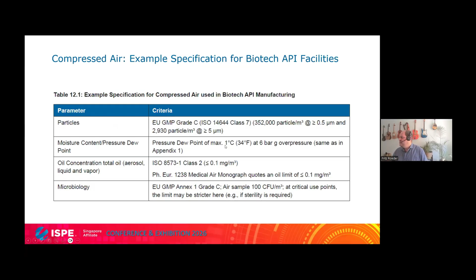Last but not least, we have two slides to go. This is the sterile slide here. The example is somewhat longer, of course. Here we have the clean room down to class A, but we say we don't need class A conditions in our compressed air pipe. We put a base quality of grade C in there, and if you need a higher spec in class B or class A because you have an outlet there, then you just apply this spec locally at this one outlet. This is pretty interesting because in water systems that would never be allowed.